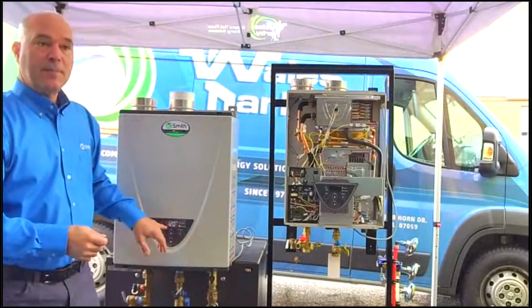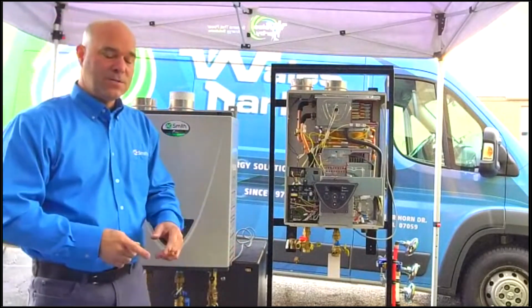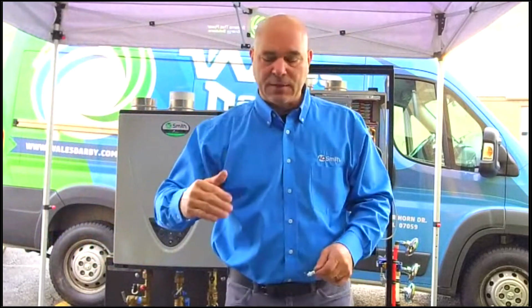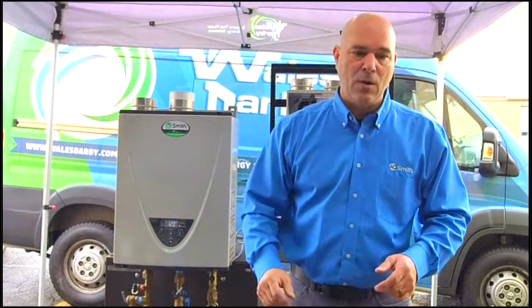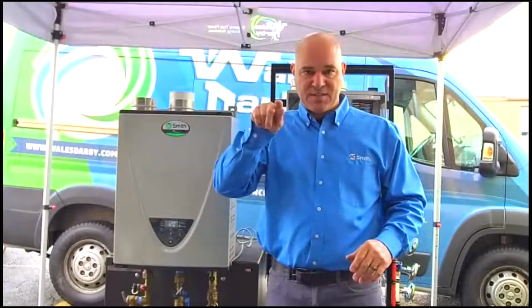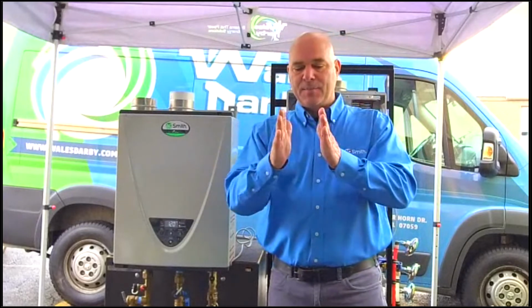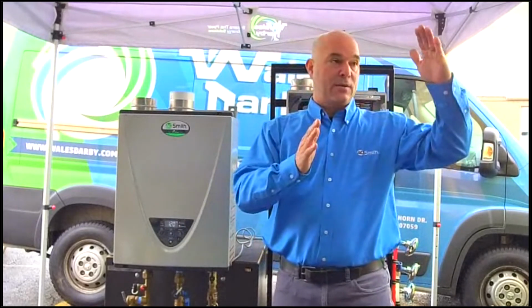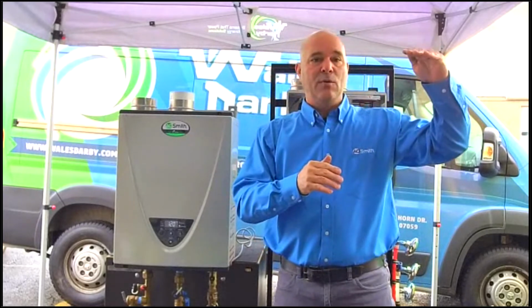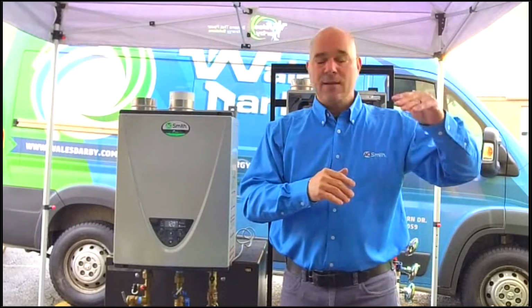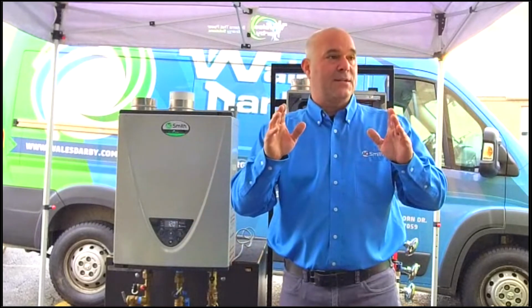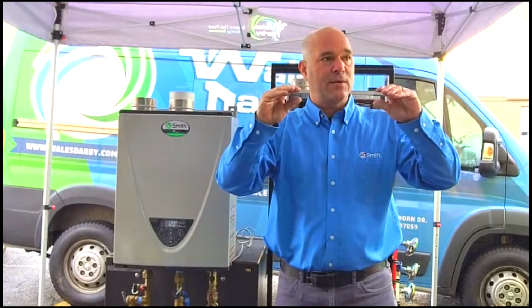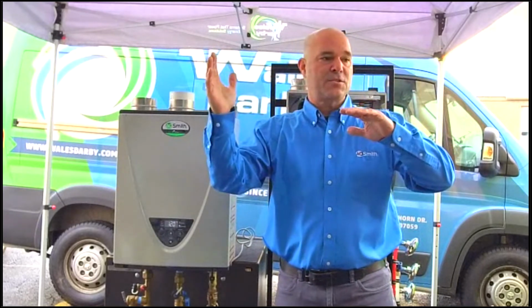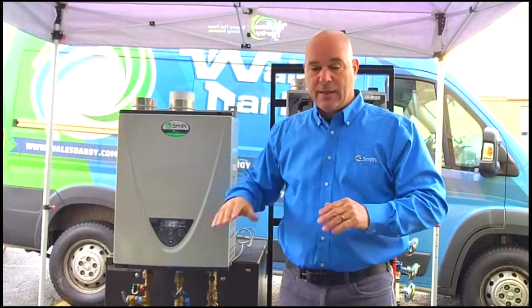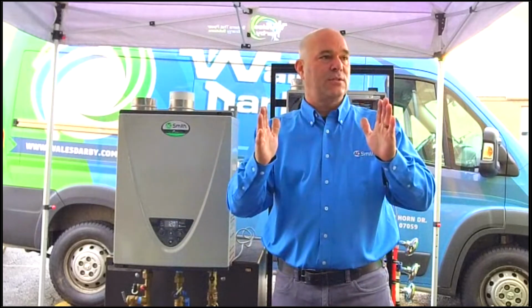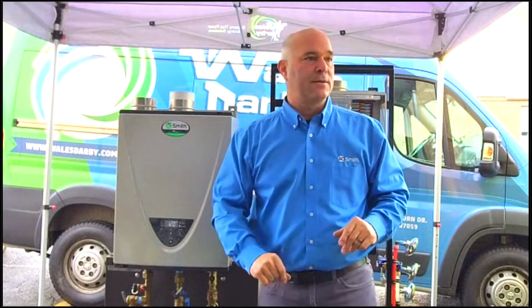We speak numbers here. We don't speak English. It's numbers for codes. Internally, if you get deep into the control, and there is a history in here, a perfect flame to this control would be a number 6. If I go out of that number 6 range, whether I go below that or above it, most of the time it'll go above it. If it gets to a number 15, it will become a hard lockout. Okay, so that's what that air fuel ratio rod is doing. It's babysitting the target temperature in the chamber, and based on that, it's going to either pulse combustion blower, pulse gas valves, and it will automatically adjust, and it has a range that it will operate within before it will allow it to shut off.